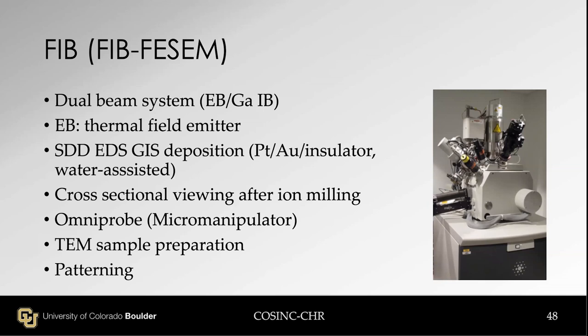The instrument looks like this. So what we have is a dual beam system - electron beam, gallium ion beam system. The electron beam is a thermal field emitter, meaning it's a field emission SEM, so it's better than a tungsten filament SEM. There's an EDS detector, and attached deposition - we can deposit platinum, gold, insulator which is SiO2, and also water-assisted deposition is possible.